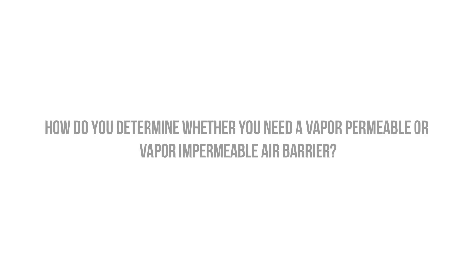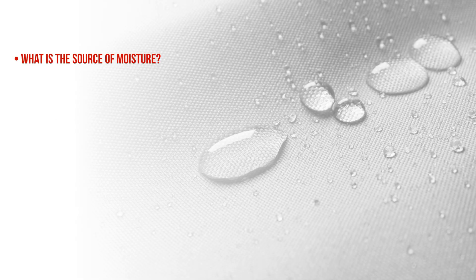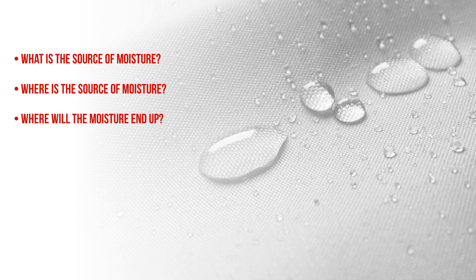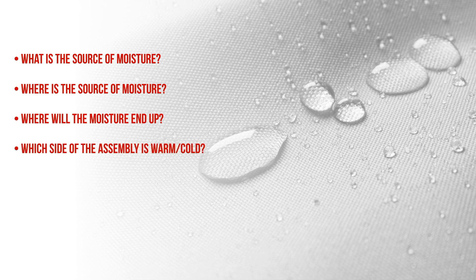So how do you determine whether you need a vapor permeable or vapor impermeable air barrier, or just a regular vapor barrier? We need to ask: What is the source of moisture — is it humid air or damp concrete? Where is the source — inside or outside? Where will the moisture end up — is it moving inward or outward? What is the first condensing surface — the roof, walls, or floors? Which side of the building is warm and which is cold? This is usually determined by climate, but day and night cycles also matter, as in high desert climates with warm days and below-freezing nights.